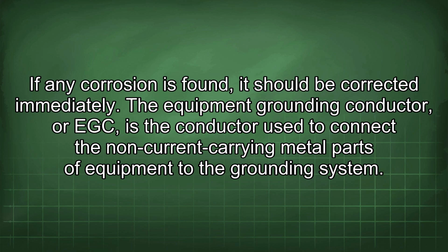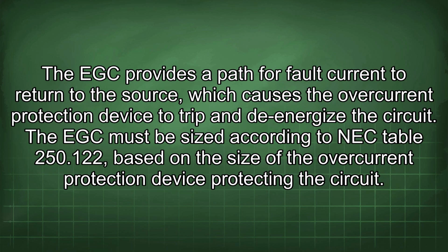The equipment grounding conductor, or EGC, is the conductor used to connect the non-current carrying metal parts of equipment to the grounding system. The EGC provides a path for fault current to return to the source, which causes the overcurrent protection device to trip and de-energize the circuit. The EGC must be sized according to NEC Table 250.122, based on the size of the overcurrent protection device protecting the circuit.